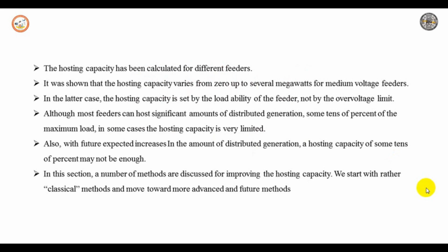The hosting capacity has been calculated for different feeders. It was shown that the hosting capacity varies from 0 up to several megawatts for a medium voltage feeder. In the latter case, the hosting capacity is set by the loadability of the feeder, not by the over voltage limit. Although most feeders can host a significant amount of distributed generation, some tens of percent of maximum load, in some cases the hosting capacity is very limited.